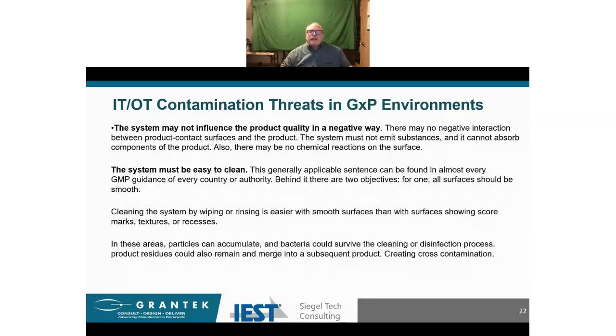So we talk about the system not influencing a product in any negative way. There must be no negative interaction between the product contact surface and the product. It must not emit substances. It must not outgas, and it cannot absorb the components of the product. There must be no chemical reaction to the surfaces. The surfaces shouldn't be discolored. And the system must be easy to clean.